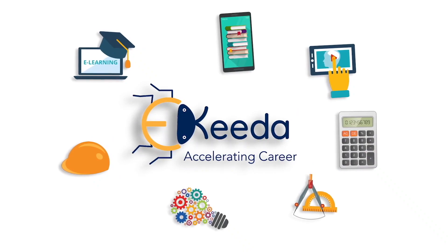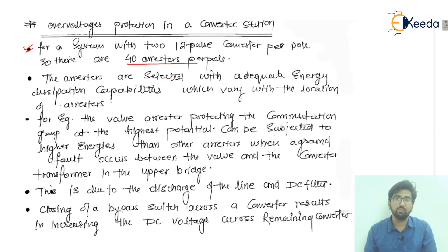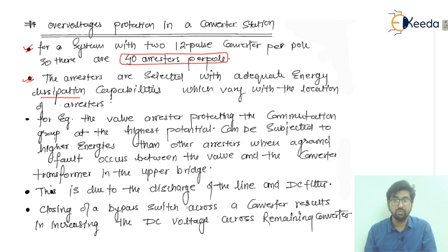For a system with two 12-pulse converters per pole, there are 40 arrestors per pole. So if we are talking about the 12-pulse converter, we are going to have 40 arrestors per pole. The arrestors are selected with adequate energy dissipation capabilities, which vary with the location of the arrestors.